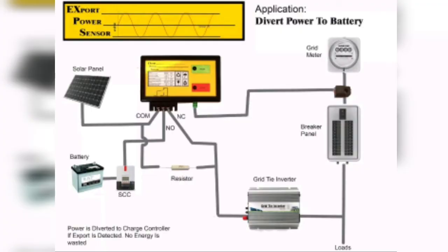Here is another application where the normally open terminal is connected to a charge controller. So every time an export is detected, the power going to the grid tie inverter is reduced, diverting the power to charge the battery.